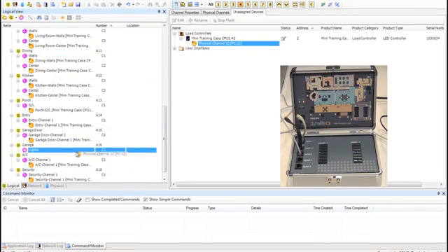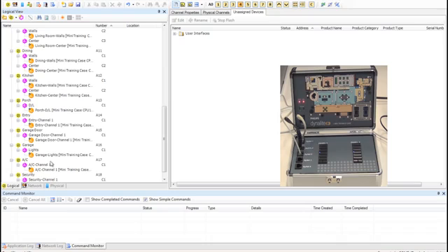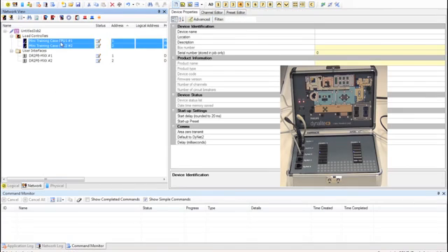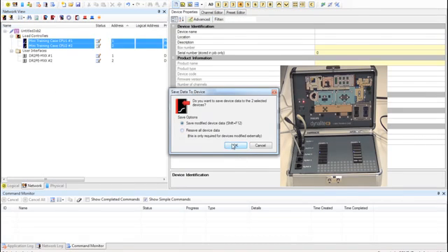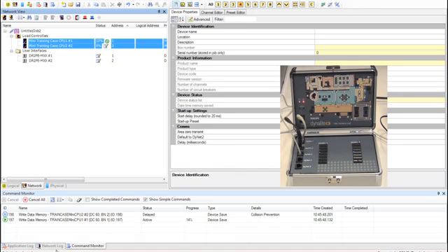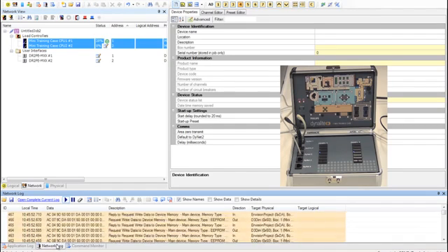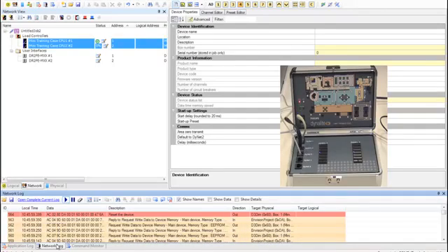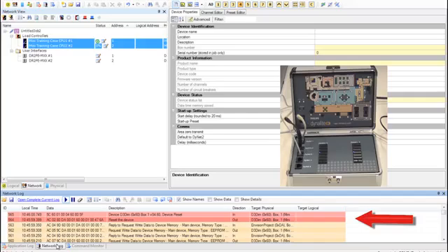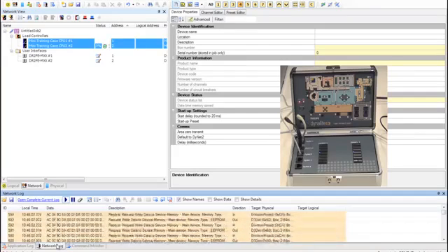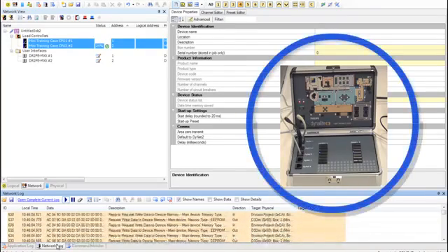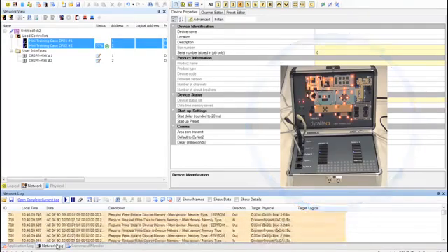Once you have completed all of that flashing, then you can press F8 to toggle to the Network tab and then download that information to your devices. We can see the network monitor going crazy there. That's downloading all of the information to each device. When you see the 2 red lines in the network window, that is your sign that it has completed that. What you will see in the real world too is the lights will go on and off. That's because when you dump the configuration to the devices, the last thing that will happen is the device reboots.